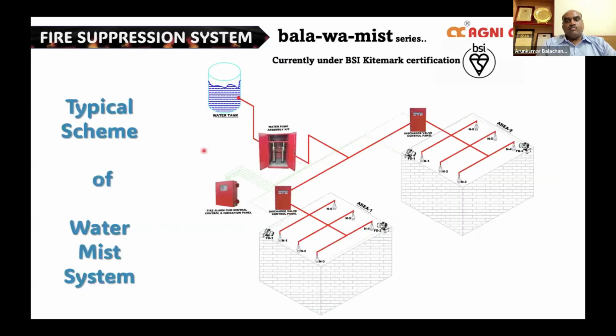This is a typical scheme of the water mist system where we have a small water tank where distilled water can be stored. The pump assembly kit can be low pressure, intermediate pressure, or high pressure, and it comes on a skid with the pump controlling mechanism. And then near the risk area, we have the discharge control panels, which will monitor the pressure and flow of water into the particular risk area. Currently, Bala-wa-mist series are under BSI Kitemark certification for global usage.